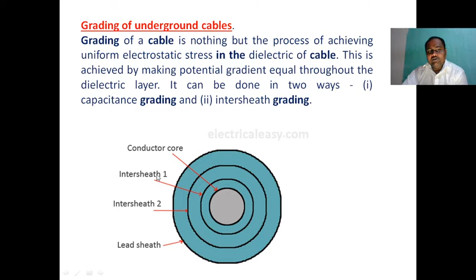First we study capacitance grading. The process of achieving uniformity in the dielectric stress by using layers of different dielectrics is known as capacitance grading. In capacitance grading, the homogeneous dielectric is replaced by a composite dielectric. The composite dielectric consists of various layers of different dielectrics in such a manner that the relative permittivity epsilon r of any layer is inversely proportional to its distance from the center. Under such conditions, the potential gradient at any point in the dielectric is constant and independent of its distance from the center. In other words, the dielectric stress in the cable is the same everywhere and the grading is ideal.